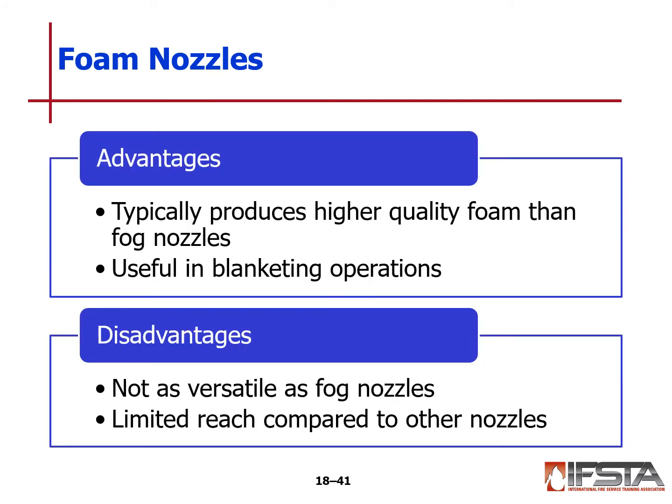So some advantages of your foam nozzles: typically produces a high quality foam as opposed to fog nozzles, and they're useful in blanketing type operations. Disadvantages, they're not as versatile as your fog nozzle, and you have limited reach compared to other nozzles.